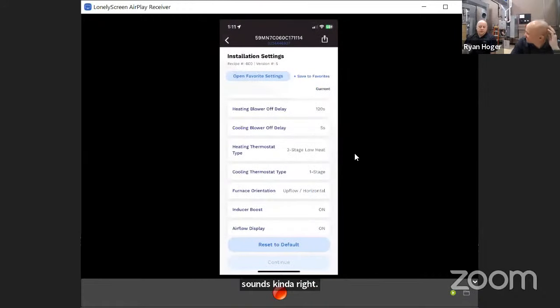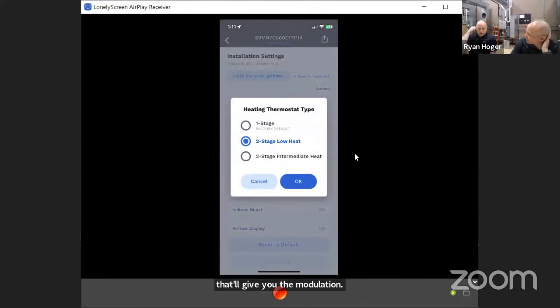And if you use a single stage stat, that'll give you the modulation. So if you hook up a single stage stat on the modulating furnace, that will give you full modulation on that furnace. You know, similar to when you have the Infinity control, but it will not be as quick reacting and as accurate as if you had the Infinity control. That's a lot better. But that does work with a single stage thermostat, standard thermostat also, just not as well.